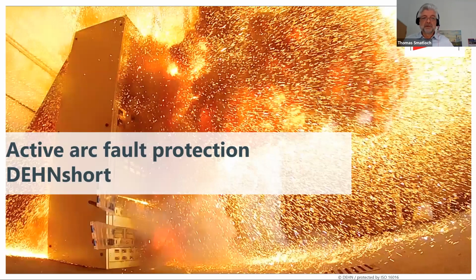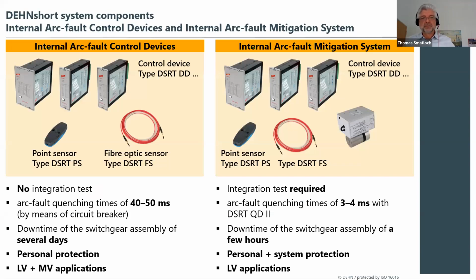Yeah, some words about so-called active arc fault protection under the brand name here of DEHN Short. I would like to spend some words on this as well. We have a complete program as an active protection, and as you can see here on the picture, on the left-hand side, it's a control system, consisting of a controller collecting the signals from different sensors. There we have a sensor for light, and this is combined with a sensor for current in the switchgear cabinet.